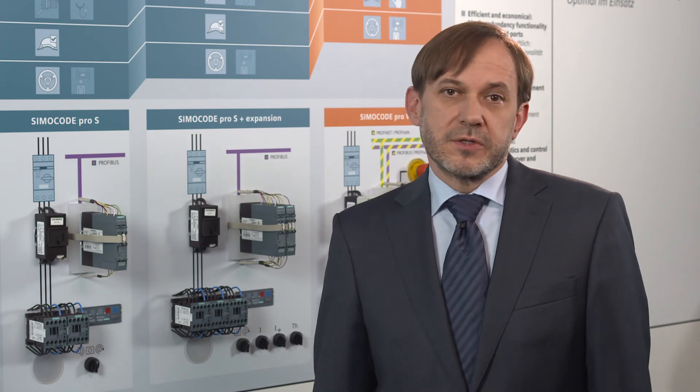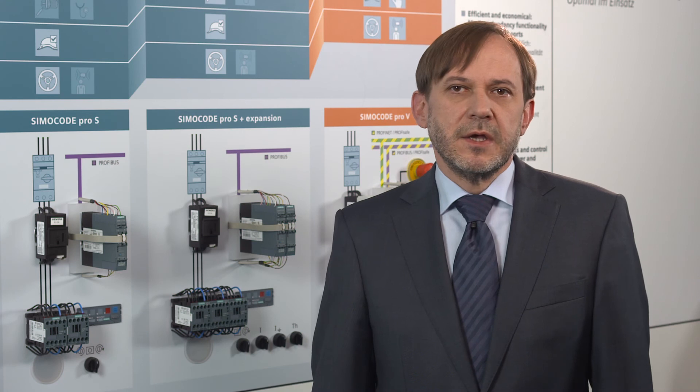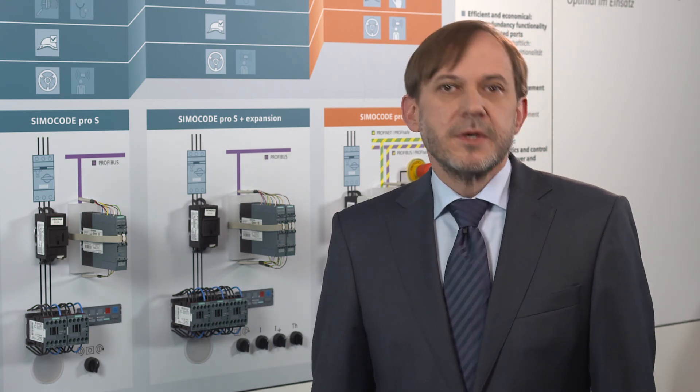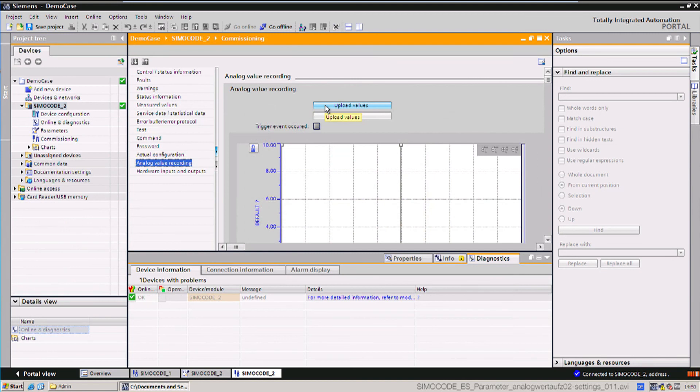You will also be convinced by the diagnostics using SIMOCODE ES in the TIA Portal. There is a host of diagnostics options that can be called up online during operation. For example, establishing the cause of a fault by reading out the error buffer or analyzing recorded current characteristics from the device.